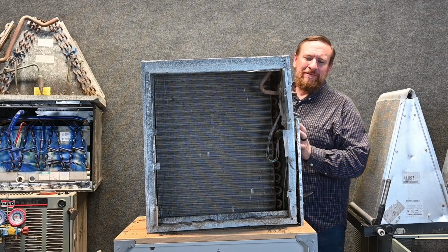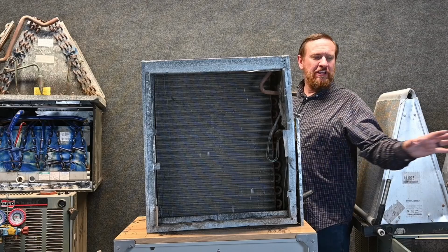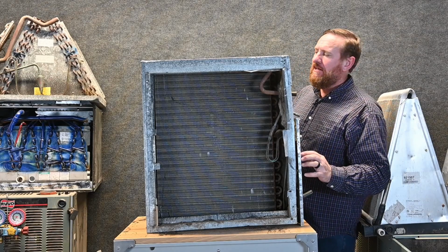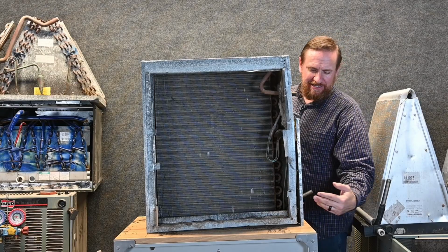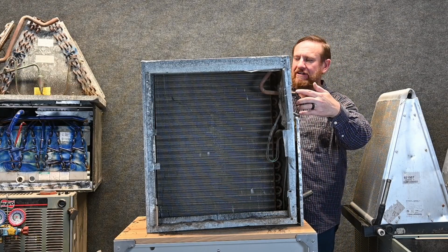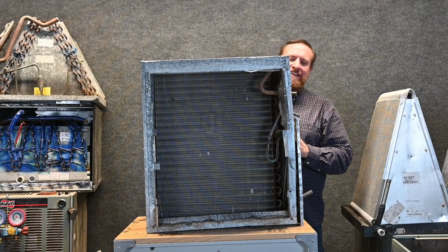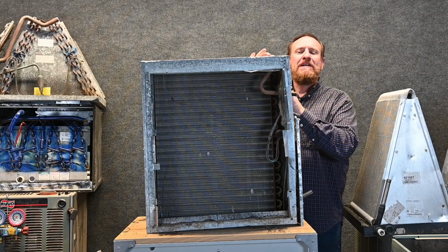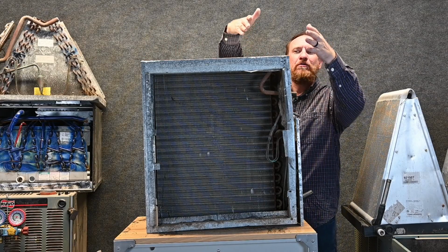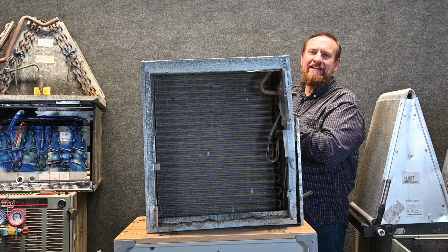One last coil we're going to talk about today, and that is a slab coil. These are used with horizontal applications, so the air is running with the horizon and moving air straight through this coil. The drain pan is down here at the bottom, so refrigerant lines are here. It does the same thing, we're absorbing heat out of the house and the humidity out of the house, but because it was a long slab coil, and this is a very small one, they get them huge, you'd have what we call a transition, or a piece of ductwork that went from the smaller unit to this larger slab coil, and then it went back down again to the ductwork.